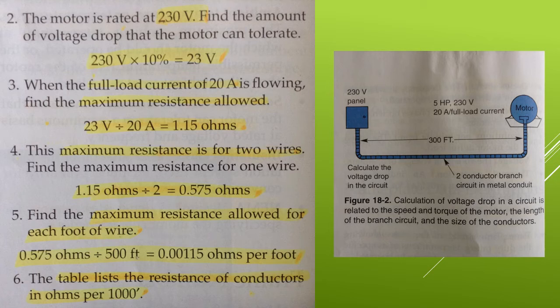Step 6, the table lists the resistance of conductors in ohms per 1,000 feet. So we have to find out what the resistance per 1,000 foot is. For that, we multiply 0.00115 ohms times 1,000 foot, which gives us 1.15 ohms per 1,000 foot.